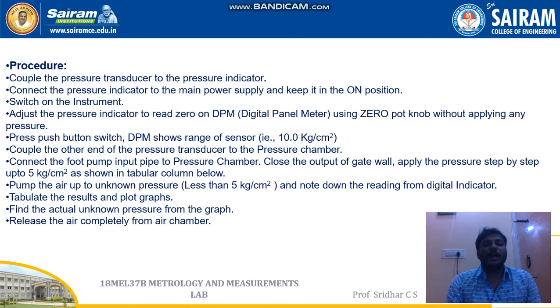Now we'll see how we're going to conduct the experiment, with the procedure. Couple the pressure transducer to the pressure indicator, connect the pressure indicator to the main power supply, keep it in the on position and switch on the instrument. These are the basic steps. Next, we need to adjust the pressure indicator, the digital panel meter, to 0 using the zero pot knob without applying any pressure. We should not apply any pressure, but we need to make the pressure indicator read 0.